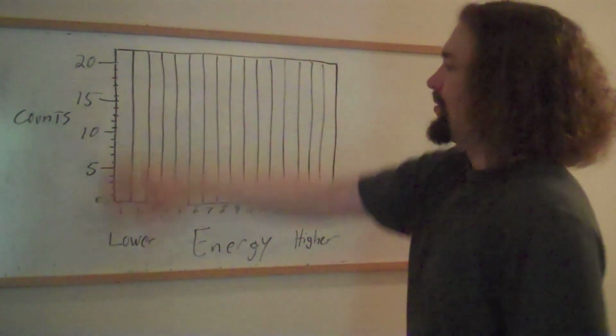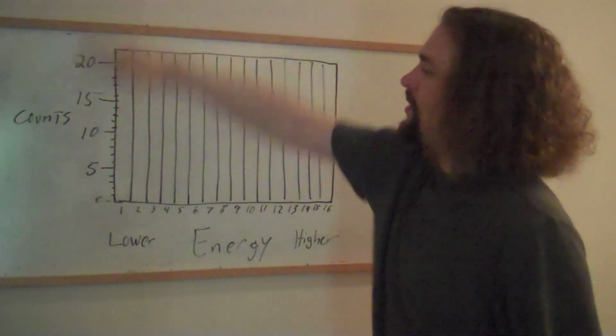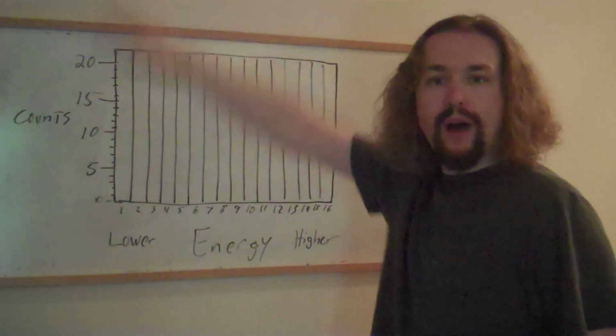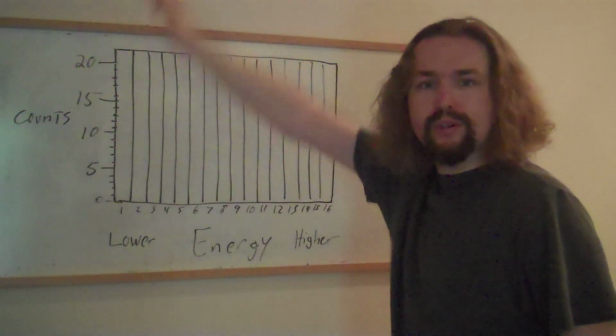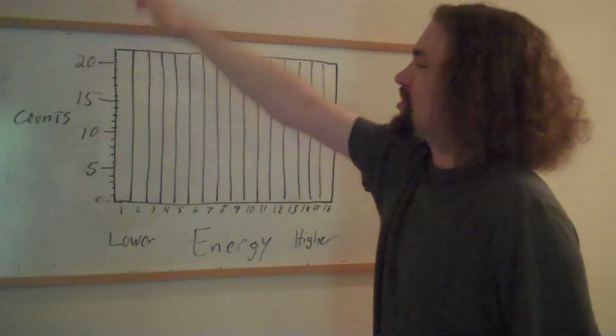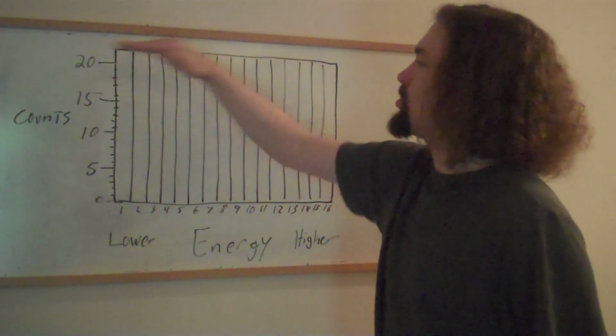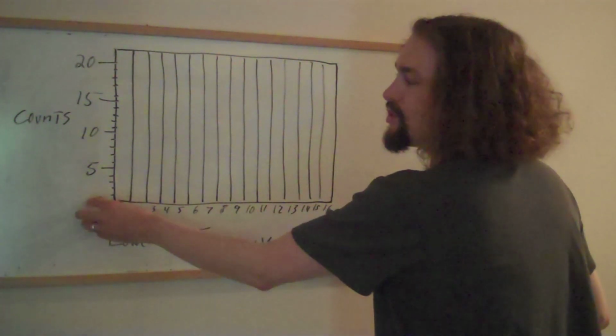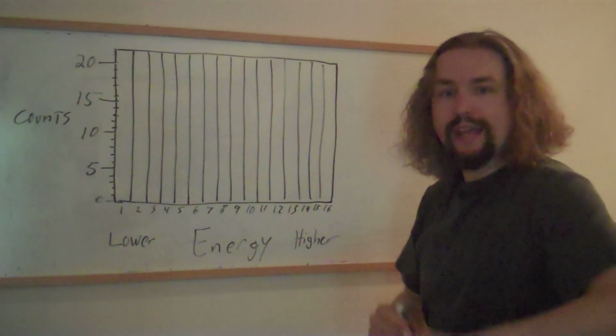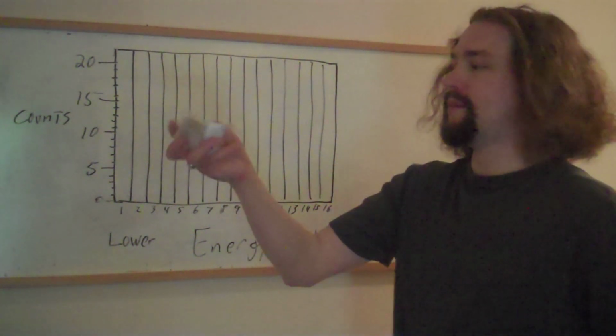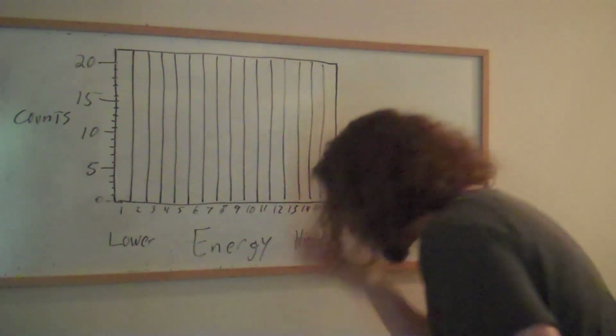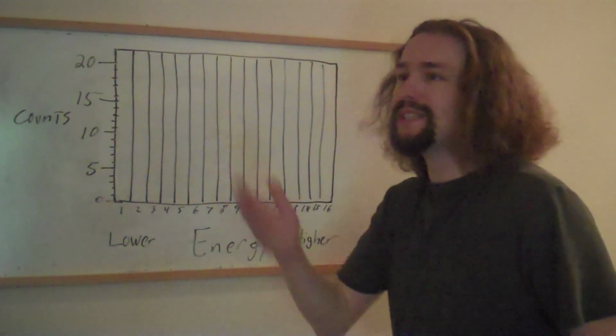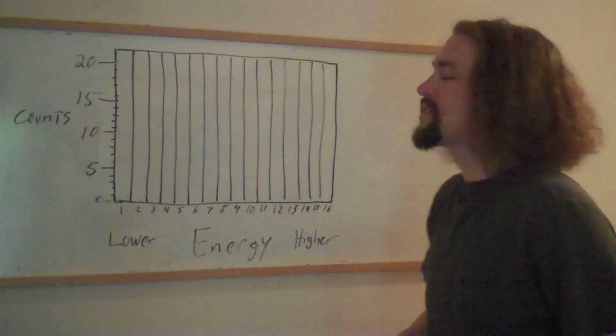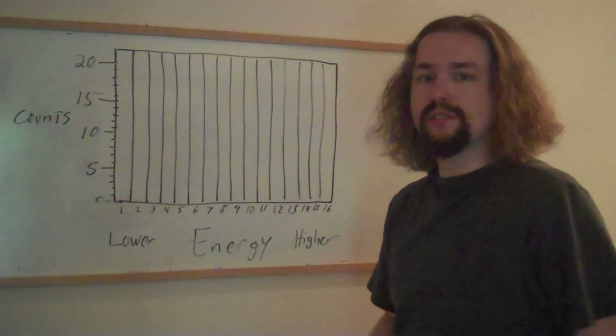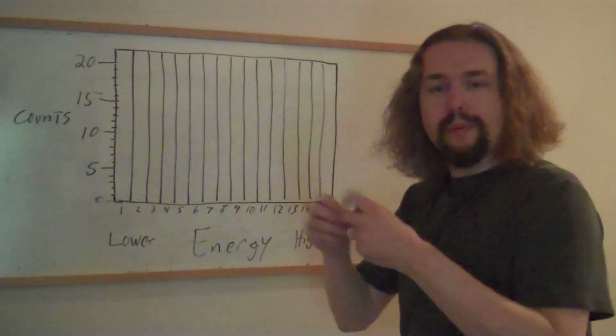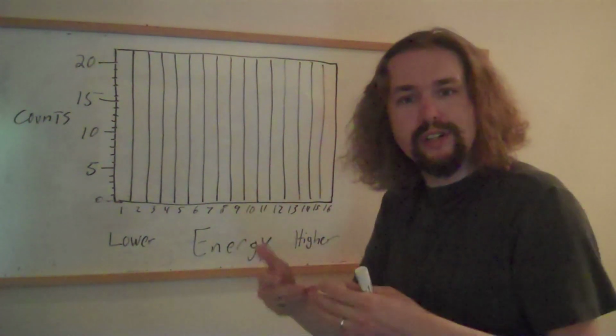Look at this. This is a graph. This represents the number of counts detected by the device. This is the Y. Remember XY graphs from middle school or something? Counts: 0, 5, 10, 15, 20. This is energy. It goes from low energy to high energy. When a gamma ray strikes something like this Bicron scintillation crystal, or in my case, a sodium iodide thallium-doped crystal, or a cesium iodide thallium-doped crystal, or any of the other little fun things that exist, you have a device called a multi-channel analyzer. And what it does is it takes those photons. Remember I told you the amount of photons emitted is proportionate to the amount of energy that hit the thing?